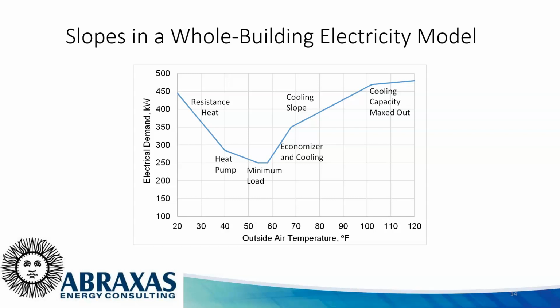If you have a heat pump building, or electrical resistance heat, you'll also see slopes on the left side where heating is required, and you'll have a relatively low slope for a portion where a heat pump might be operating, and if the heat pump runs out of capacity or you need to add resistance heat, you'll go to a steeper slope on the left side, as shown in the chart here. So with this in mind, there are different types of models that can be used. These are called change point models when we're modeling with interval meter data. And I'm getting to this not so much from the standpoint of CMVP, but for diagnostics.